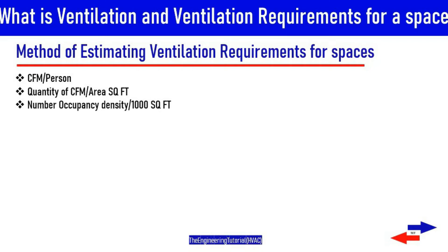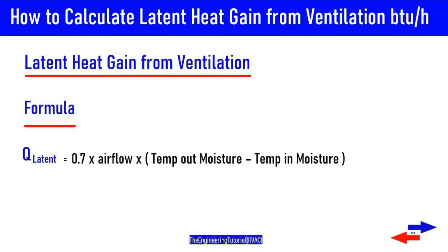The three methods for calculating ventilation requirements are: the first method involves multiplying the number of people in the space by the quantity of CFM per person; the second method involves multiplying the area in square feet by the CFM per square foot rate; and the third method involves multiplying the occupancy density per 1000 square feet. In these examples, the latent heat gain from ventilation is calculated using the same equation as for infiltration.